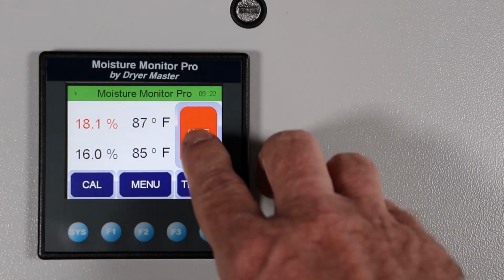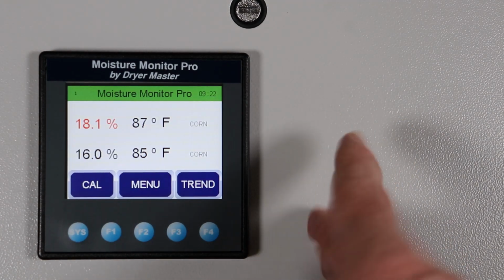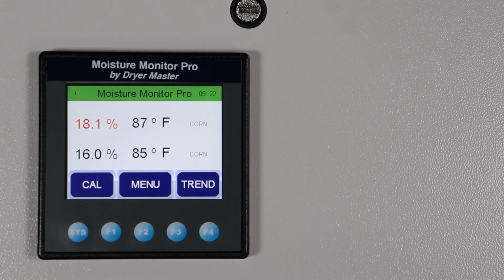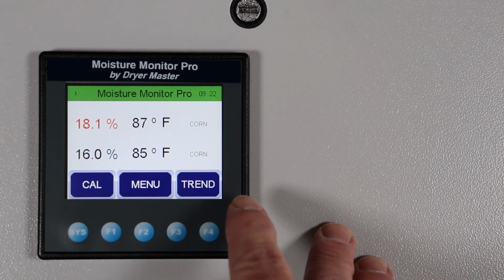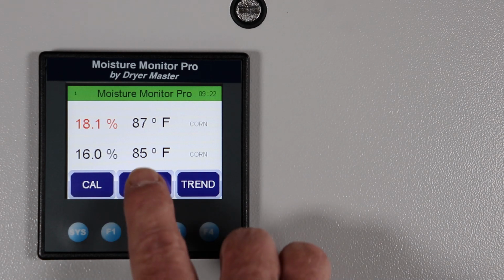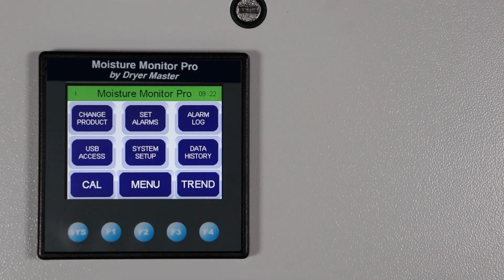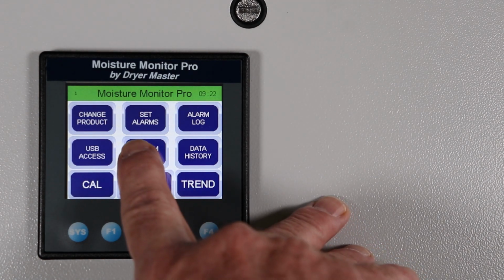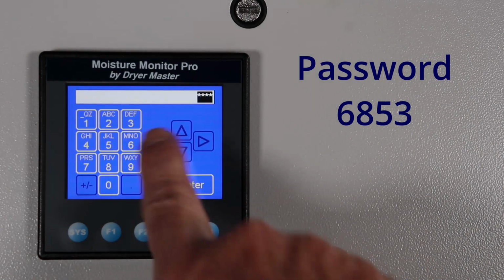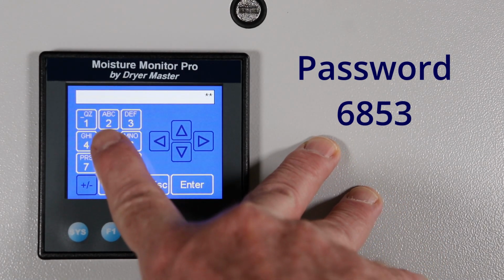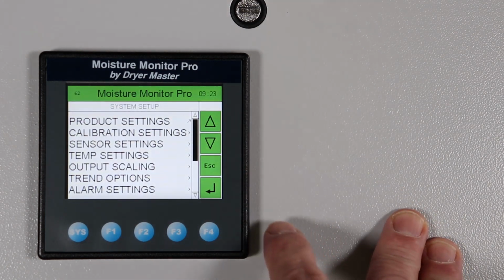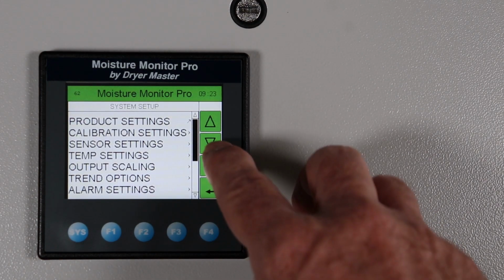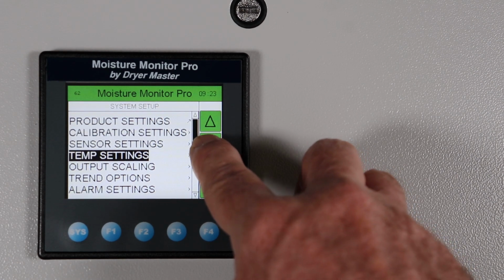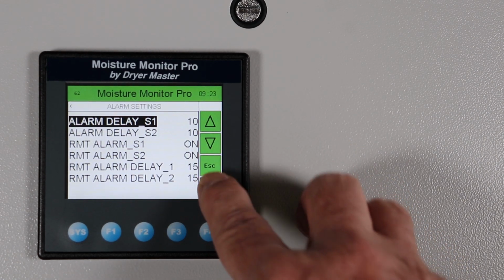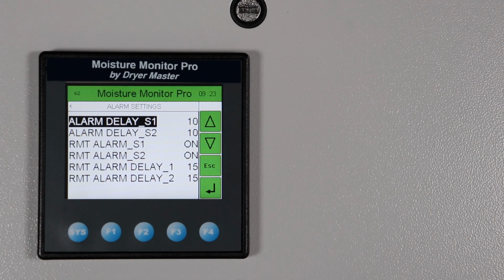There we go. If I clear it, again I see it, and then I am in a warning situation. Now, I said there was an alarm delay, so that 10 seconds we saw, we can set that easily. So we're going to go now into the more detailed engineering screens. So we just hit the System Setup button, the password, 6853, enter, and this is under alarm settings, so we can use the little up and down arrows, and enter. And we've got an alarm delay here for sensor 1 and for sensor 2.